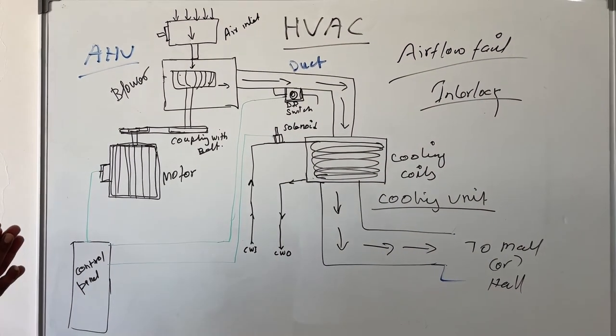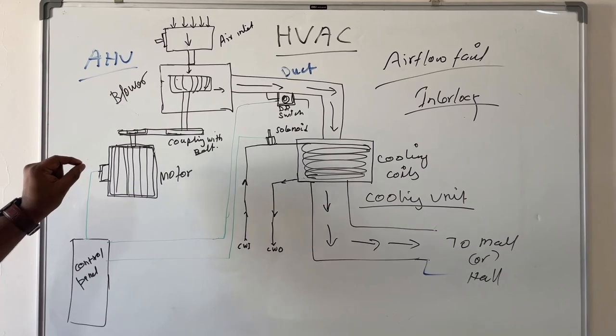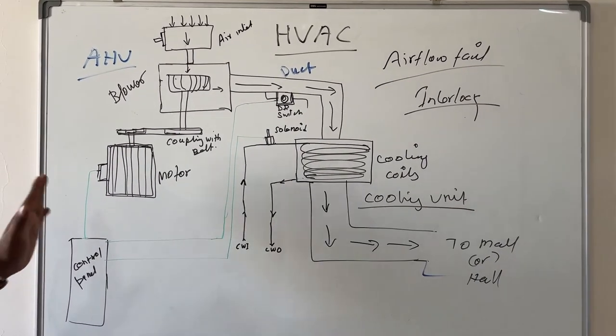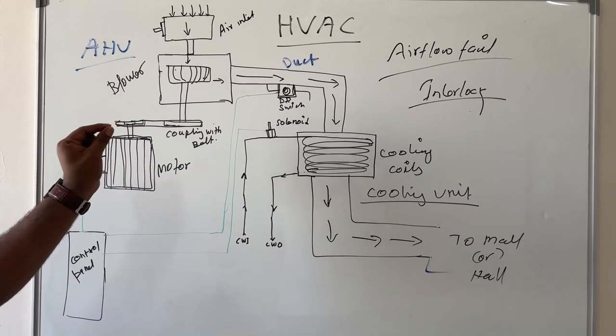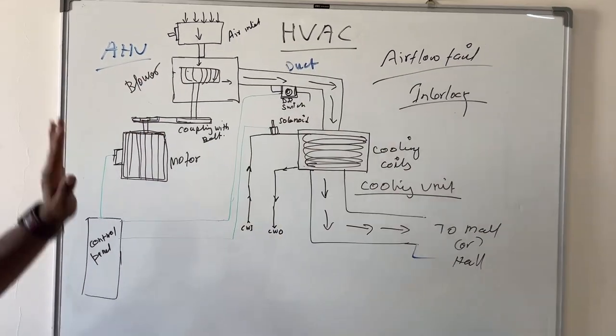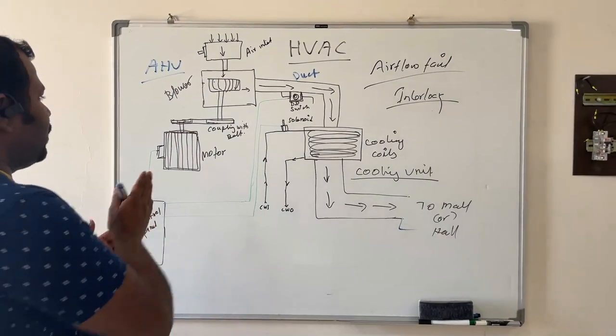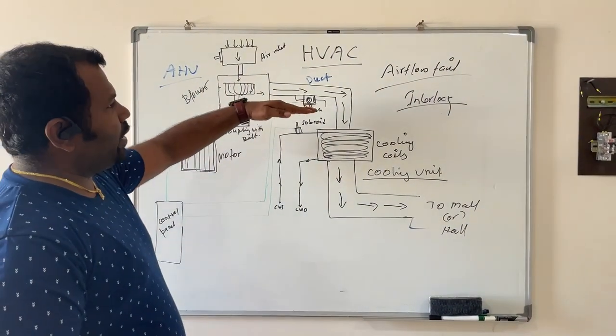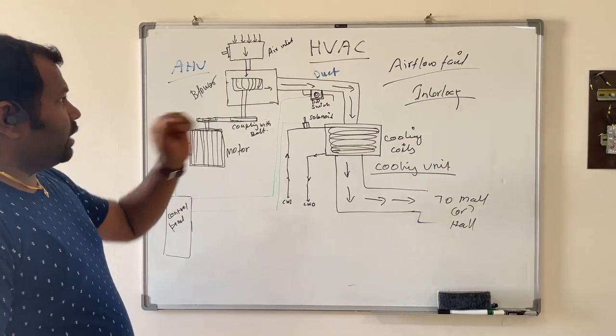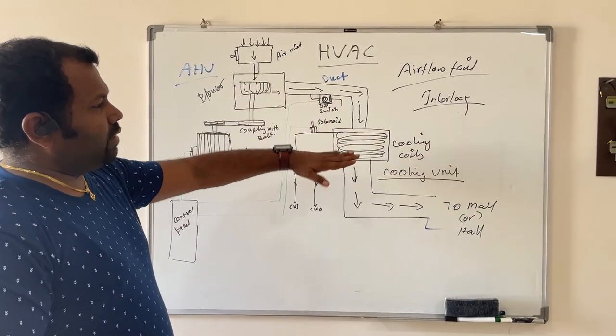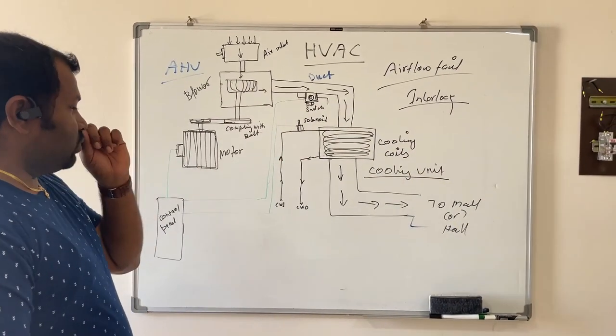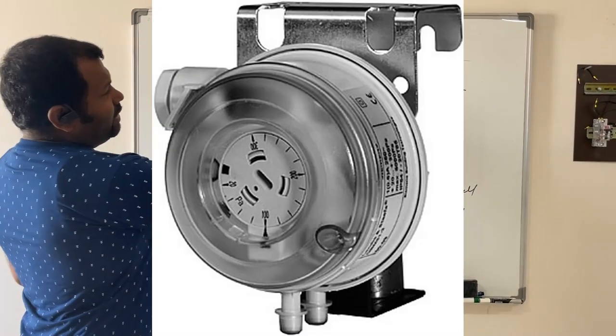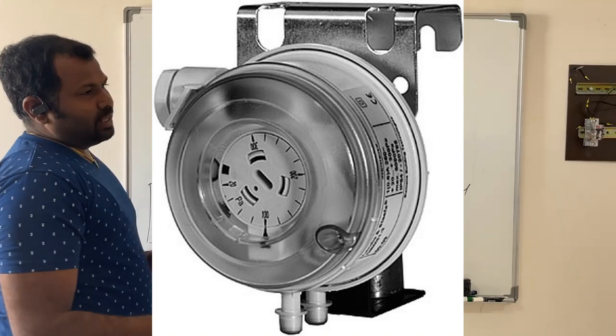An electrical signal is taken from the electrical circuit of this motor. But as mentioned, when there is a belt cut or any mechanical failure, we won't know whether the blower is working or not. So we need to monitor the airflow directly, because if the airflow is not there, there will be a problem in the cooling system.